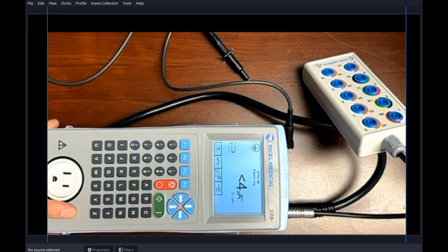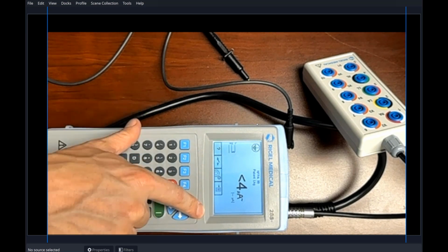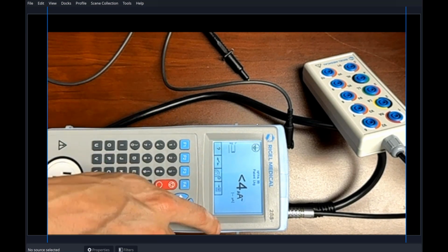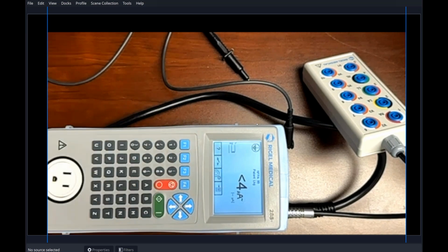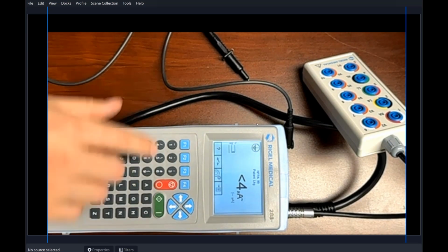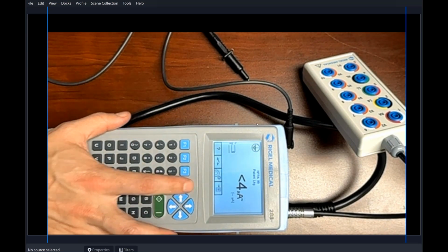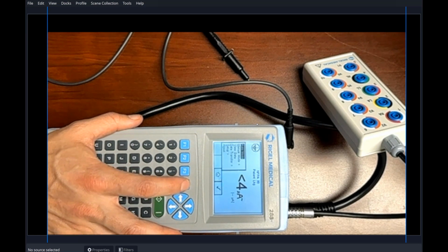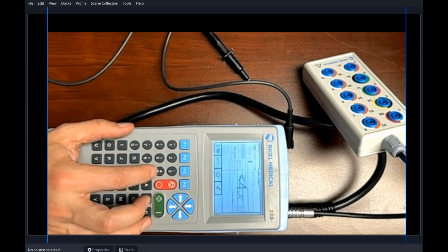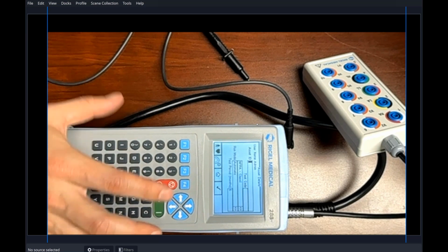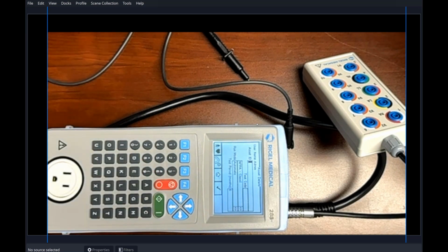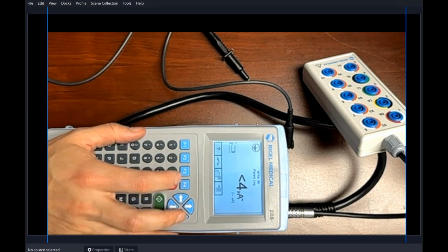So if you do need to perform any manual tests, you can create those manually and change the fault conditions within that menu setting. But for an NFPA 99 test, you only really need to run through automatic mode, key in the asset ID, and the 288 will take care of the rest in terms of the sequence, the test limits, whether it's going to pass or fail, and run through on there.